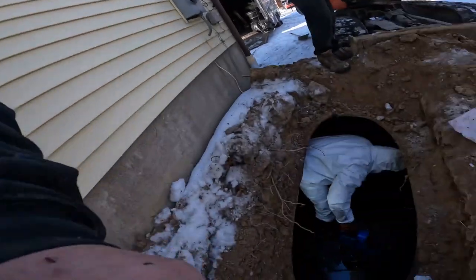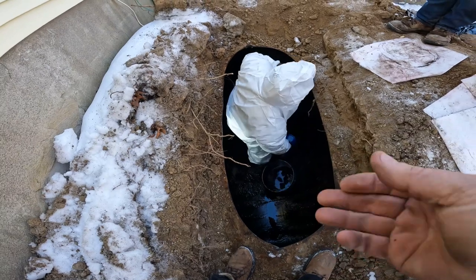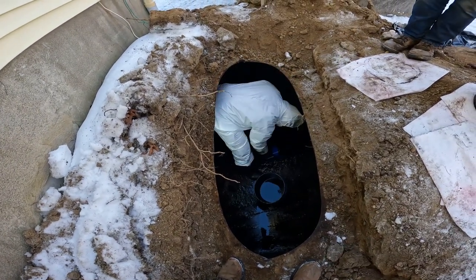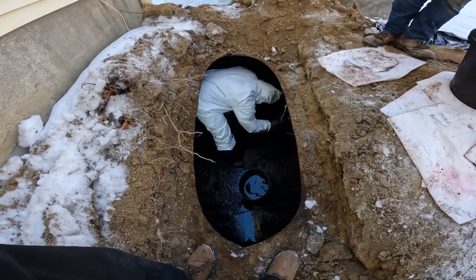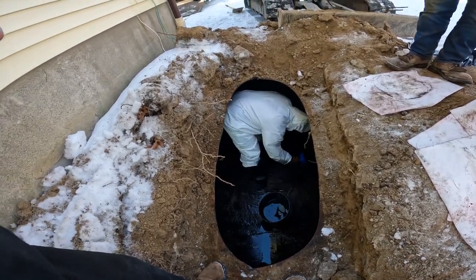Same process with an abandonment. The only difference is it's a little bit harder to see if there is an environmental impact, because you can't visually see beneath the tank or the outside of the tank. So some of the townships actually want us to drill through the bottom and procure an analysis 12 inches below the base of the vessel. I don't know whether this township requires it. I'll check the file. If they do, we also have to look, because a lot of the townships, if that is the case, the inspector wants to see you do it. I guess because they don't believe you. Why else?